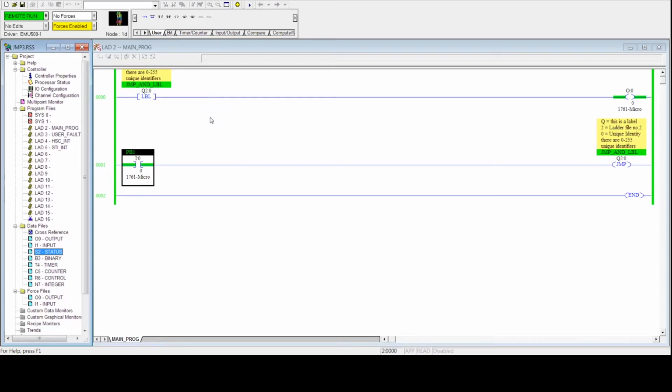That is because in PLCs, unlike other computer programming languages, we cannot jump backwards. This is a safety feature to keep us from going into infinite loops. There are ways to get into infinite loops in PLCs, and we might explore that later, but just know for the jump instruction, you cannot jump backwards. And this is why. You don't want to get caught in an infinite loop.